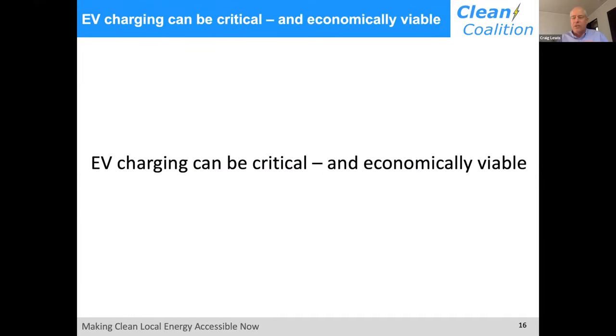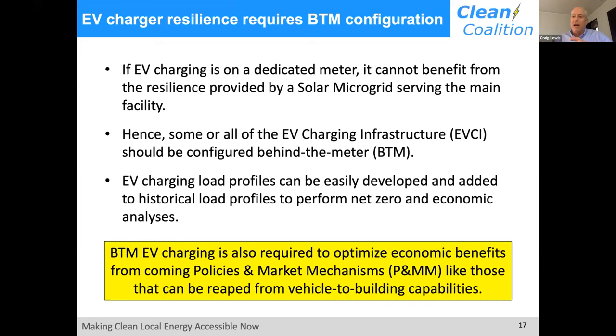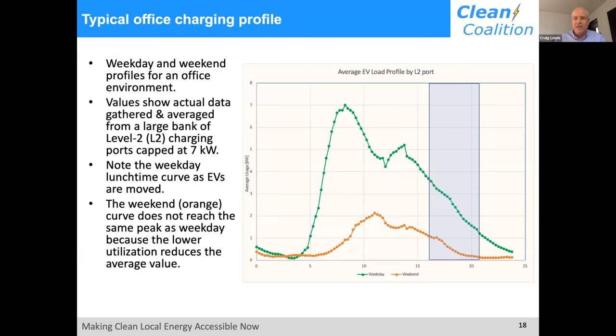I want to make the point that electric vehicle charging can be a critical load, and it can also be a way to optimize economics. To do that, you need a behind-the-meter configuration for your EV charging infrastructure. If you go with a charge-ready program through Southern California Edison, or whatever PG&E's version is, where they install the EV charging, it has its own meter and will not be supported by a solar microgrid. If the grid goes down, that EV charging is not accessible—there's no energy going into those chargers. So if you want resilience for your EV charging infrastructure, you need to design it behind the meter, and design it very intelligently.